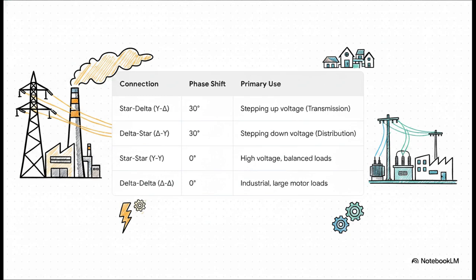On the big grid, power isn't simple, it's three-phase. To handle that, transformers have to be connected in special ways. The two you'll see most are for stepping voltage up and down. Right at the power plant, they use a star-delta connection to jack the voltage way up for efficient long-distance travel. Then, when that power gets to your neighborhood, a delta-star connection brings it back down to a safe level for all of us to use.